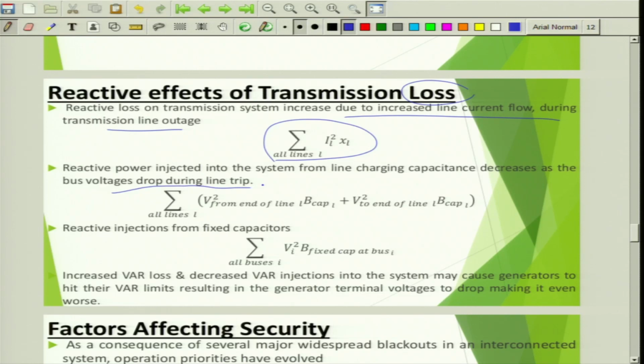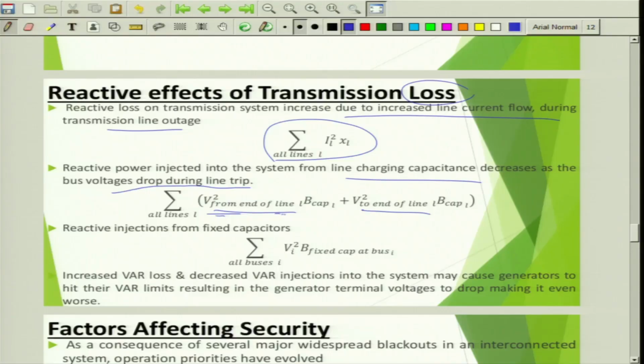So there is a line charging capacitance present because that line is out. Now that line charging capacitance is also not present. So that means there is a transmission line, from the starting point of the line to the ending point of the line, there is a significant amount of charging capacitance which was present. Now that is not present, that has been taken out. So this represents the reactive power V square by X, or V square into susceptance, at the starting point and at the ending point. So now this has been taken off.